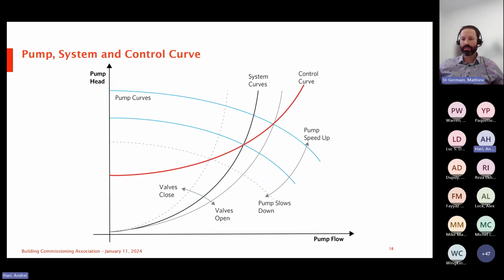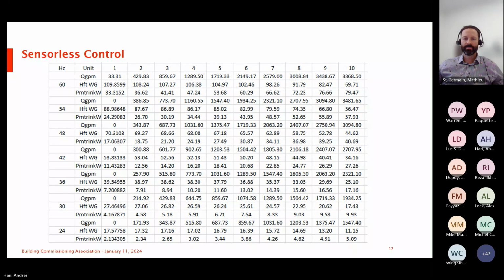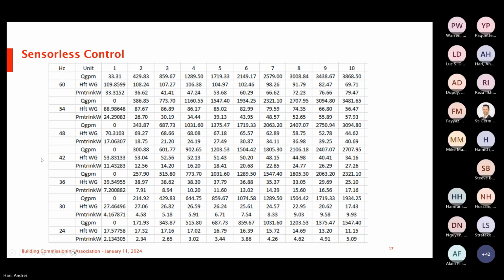Andrei, there's another quick question. Go ahead. So I was wondering, how do you measure the RPM of the pump? Oh, the RPM is just measured from the drive itself. It's taking that rotation, the frequency. So there's no rotational sensor on the shaft of the pump? No, there's nothing like that. The drive reads this itself, and it just equates that frequency to the speed itself. Okay, thank you.